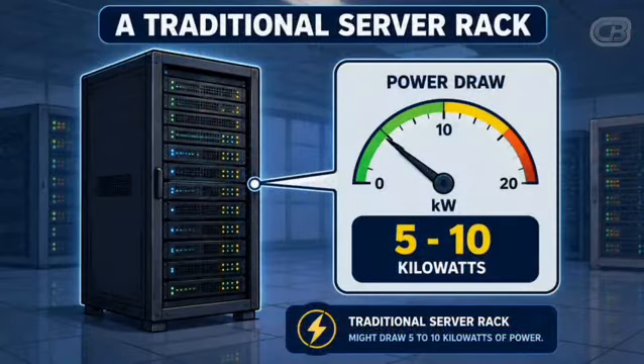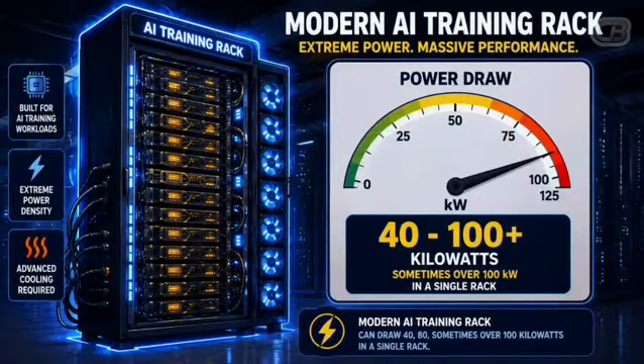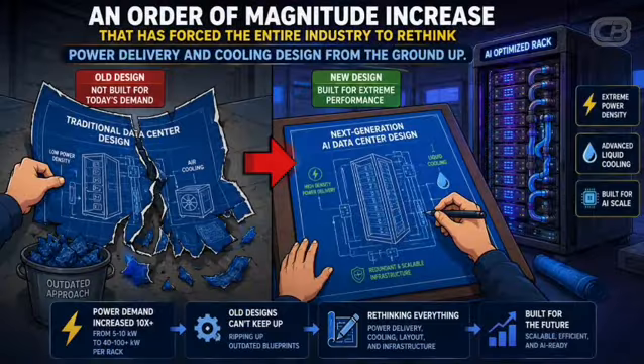A traditional server rack might draw 5 to 10 kilowatts of power. A modern AI training rack can draw 40, 80, sometimes over 100 kilowatts in a single rack - an order of magnitude increase that has forced the entire industry to rethink power delivery and cooling design from the ground up.